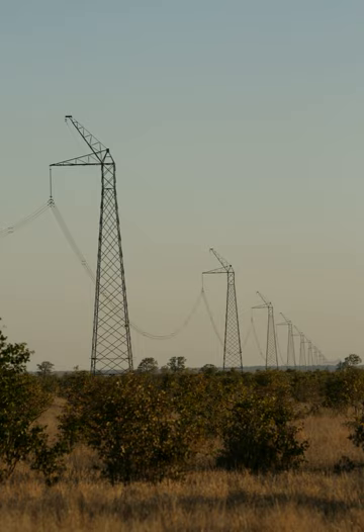Power is supplied to the SWER line by an isolating transformer of up to 300 kVA. This transformer isolates the grid from ground or earth, and changes the grid voltage — typically 22 or 33 kV line to line — to the SWER voltage, typically 12.7 or 19.1 kV line to earth.